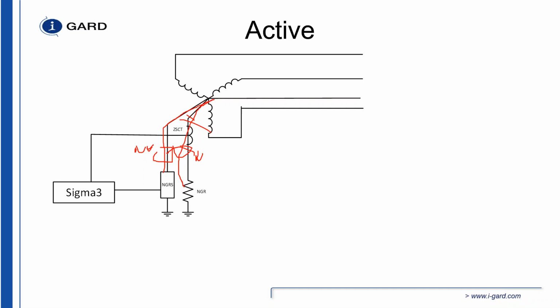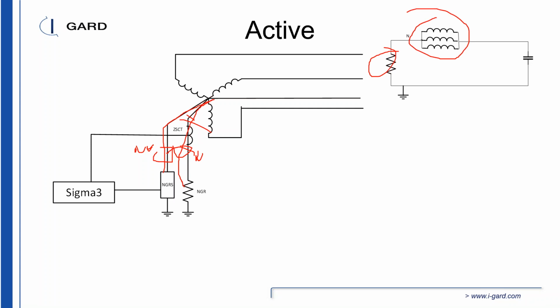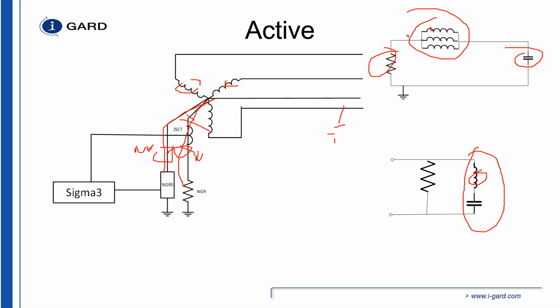The way this works is we put in a signal of a higher frequency. When we put in a signal of a higher frequency, we end up with a circuit that looks like this. We have the NGR here. We have the inductance of the transformers here, and the capacitive coupling of the phase conductors to ground. That basically comes to this equivalent circuit. So we have a resistor in parallel with an inductor in series with a capacitor. When we inject a high frequency signal, we're going to get a lot of impedance due to the inductance, and this is frequency independent, so it stays constant.